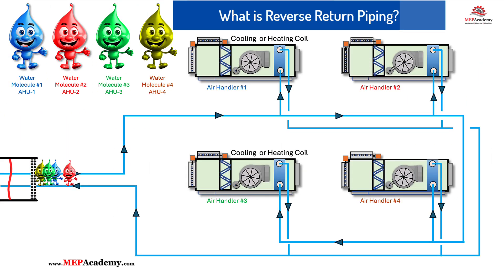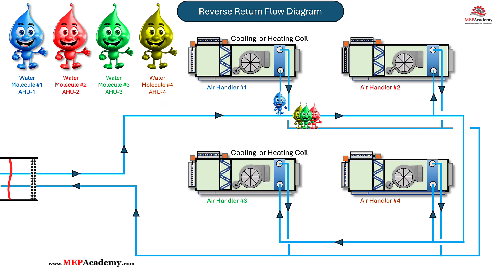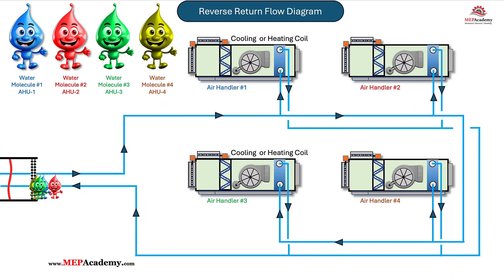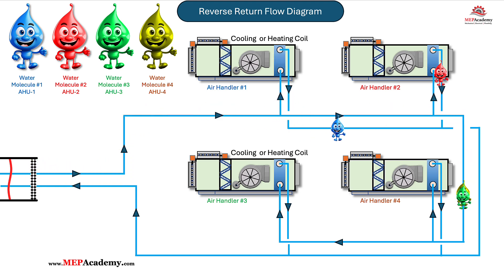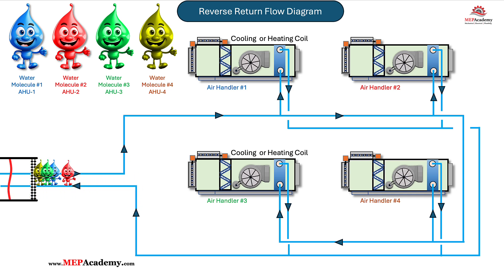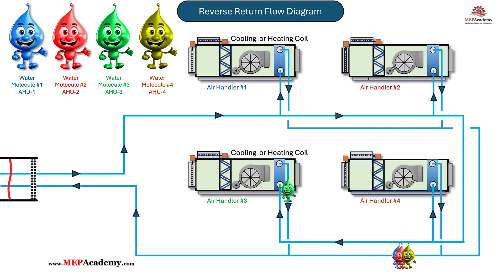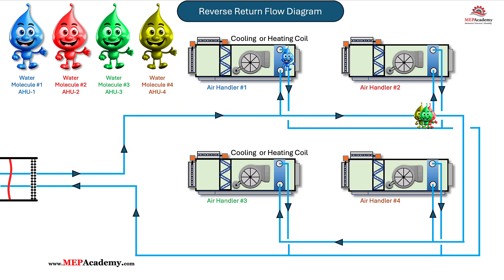What is reverse return piping? In a reverse return piping system, water flows to each terminal unit via the shortest path but returns along the longest path. Essentially, the return pipework is designed so that the last unit on the supply line is the first to return to the source. This approach results in equalized pipe lengths for each terminal unit, which is one of the defining characteristics of reverse return piping.